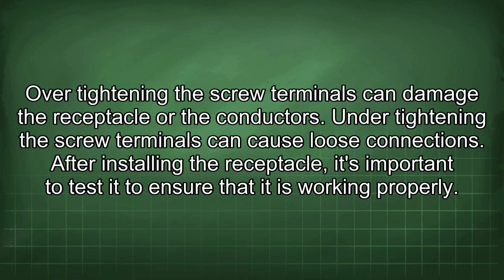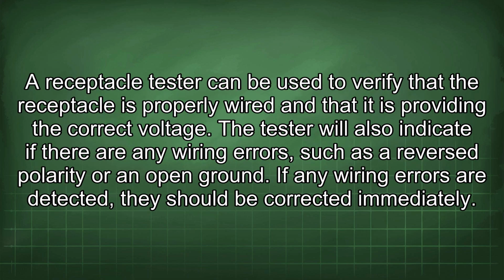After installing the receptacle, it's important to test it to ensure that it is working properly. A receptacle tester can be used to verify that the receptacle is properly wired and that it is providing the correct voltage. The tester will also indicate if there are any wiring errors, such as a reverse polarity or an open ground. If any wiring errors are detected, they should be corrected immediately.